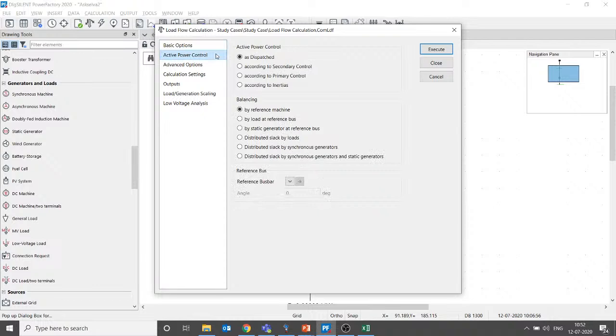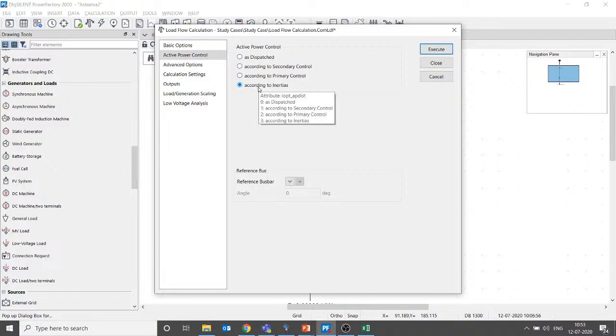If you look at active power control, that is, the dispatch, it is with respect to the reference machine, but you have other options, such as according to secondary control, primary control, or inertia. There are many other possibilities available in ETAP. These concepts are not based on the swing bus, and they reflect real-time systems more closely. Since you are from the oil and gas sector, when you are simulating multiple load flow configurations with more than one generator operating in an islanded system, you need to ensure that the real and reactive power generated by all these generators are the same. But unfortunately, when you simulate it in ETAP, that will not be the same.